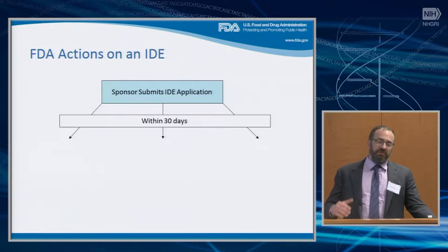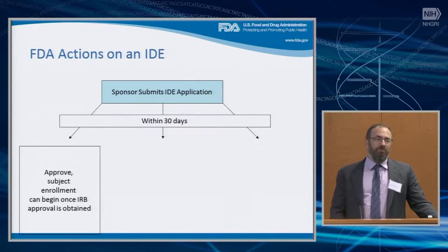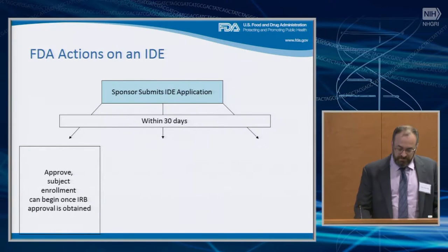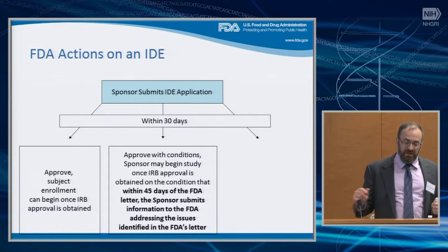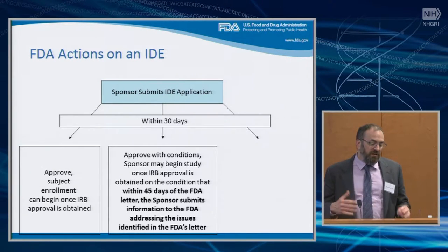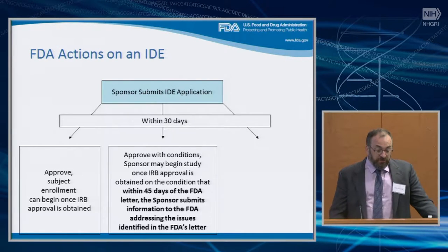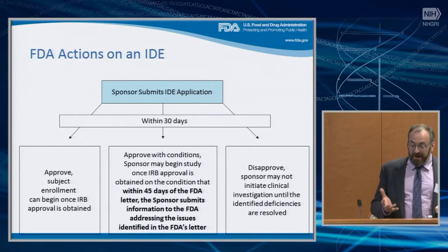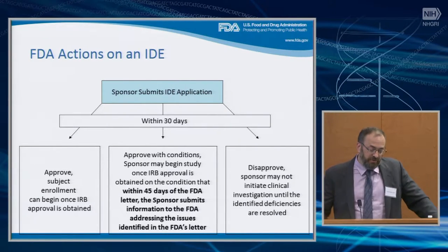FDA actions on the IDE: you've submitted your IDE, it's day 30, and you receive notification that you are one of three things. Approved — you can begin enrolling subjects once IRB approval is obtained. Approved with conditions — this means you can begin your study once you have IRB approval, but you have 45 days to make certain changes, such as changes in the informed consent document. They won't be big things like analytical validation studies, but often there are tweaks FDA will request that won't hold up the study. Third, it's rare for IVDs but you may be disapproved. If disapproved, you'll receive a letter documenting the deficiencies and the reason, and you can submit a supplement or a new IDE addressing those deficiencies.